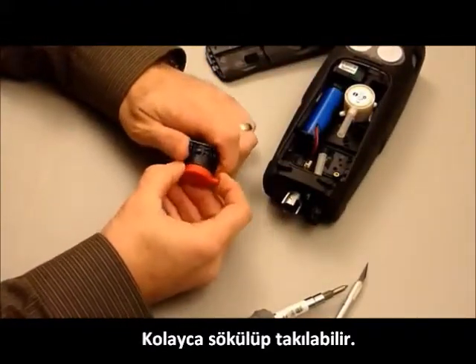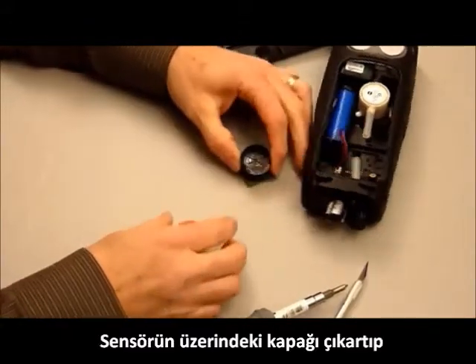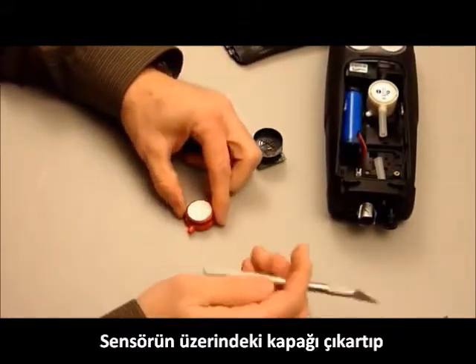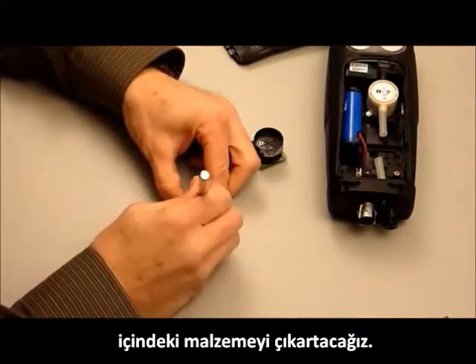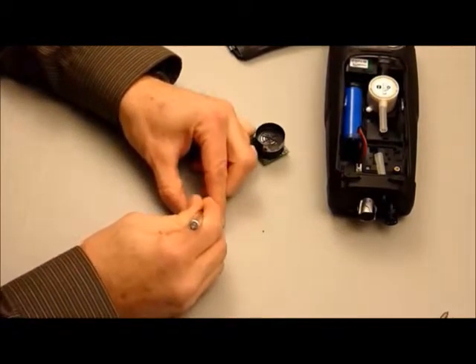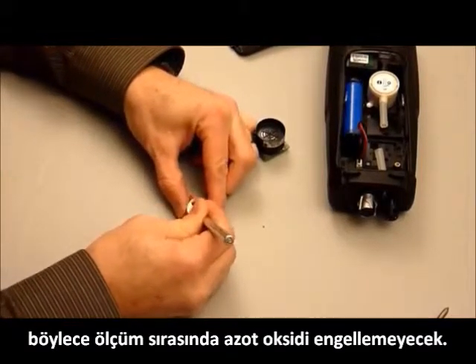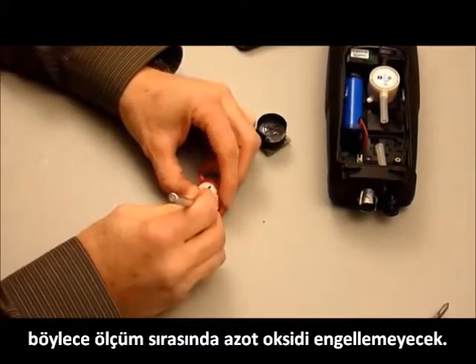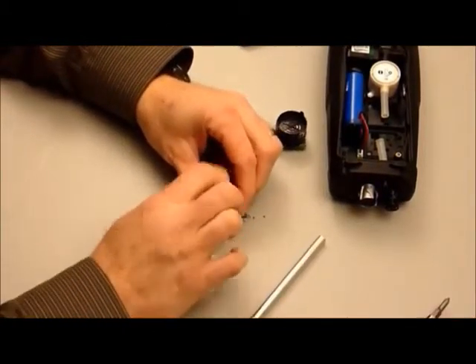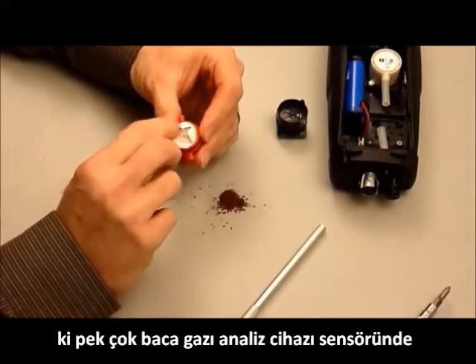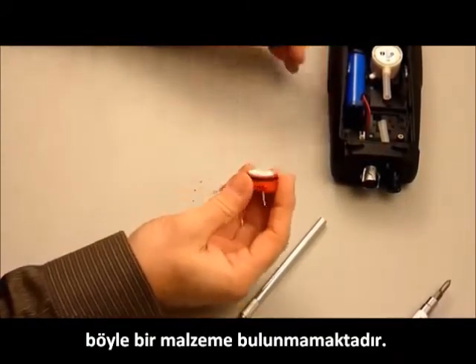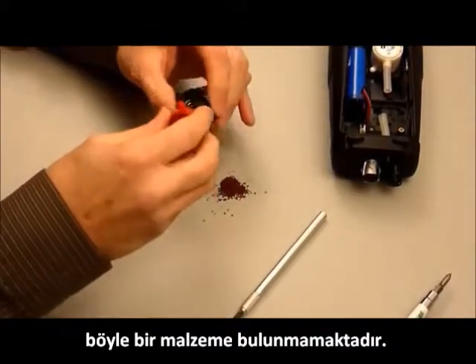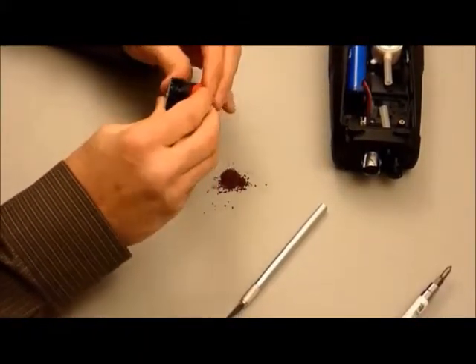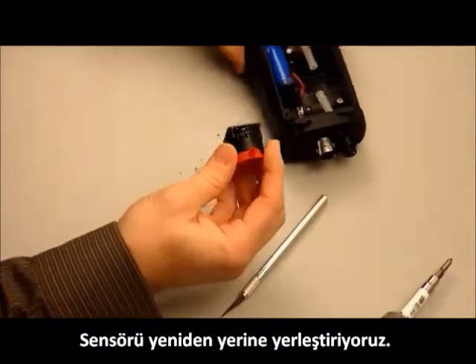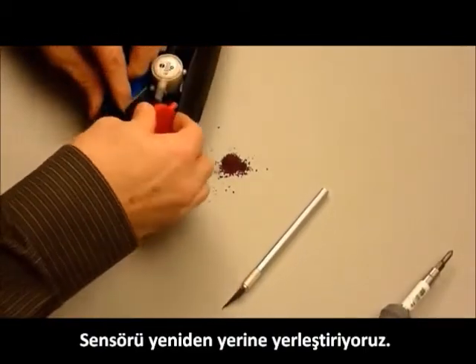What we're going to do is remove the top of the sensor and take the media out so that it will not scrub the nitric oxide during the measurement. And many flue gas analyzers use sensors that don't include this material. I'll put it back in.